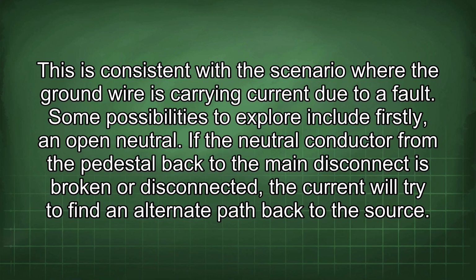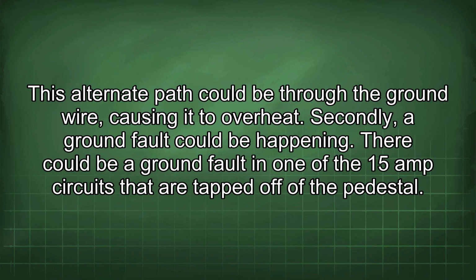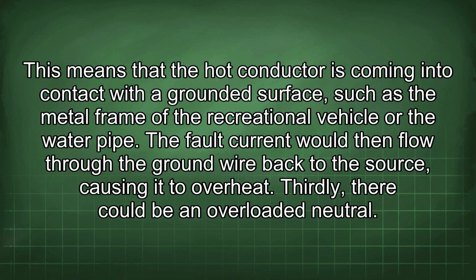Some possibilities to explore include, firstly, an open neutral. If the neutral conductor from the pedestal back to the main disconnect is broken or disconnected, the current will try to find an alternate path back to the source. This alternate path could be through the ground wire, causing it to overheat. Secondly, a ground fault could be happening. There could be a ground fault in one of the 15 amp circuits that are tapped off of the pedestal. This means that the hot conductor is coming into contact with a grounded surface, such as the metal frame of the recreational vehicle or the water pipe.